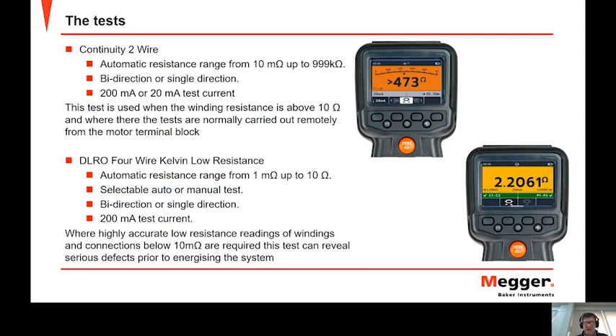So where highly accurate low resistance readings of windings and connections are required, the DLRO function must be used. So for example, if we have a winding which is around 10 milliohms, in theory the continuity test can measure that. But if one winding was 9.5 and one was 10.3 and the other was 10.8, that would calculate quite an unbalance between the phases. But on a continuity test, it wouldn't show that. They would all show as 10 milliohms. So it looks balanced. When you have the extra resolution of the 4-wire Kelvin measurement, then you can see the actual values and that they are unbalanced.